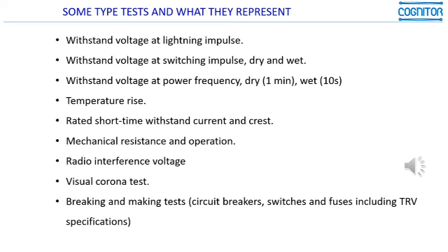Visual corona tests, breaking and make tests. Usually this is applicable only for circuit breakers or switching equipment. For switches and fuses, sometimes you also have requirements a little bit different from the main circuit breakers, but basically all these tests, break and make tests, are applicable to circuit breakers, but not to isolators.